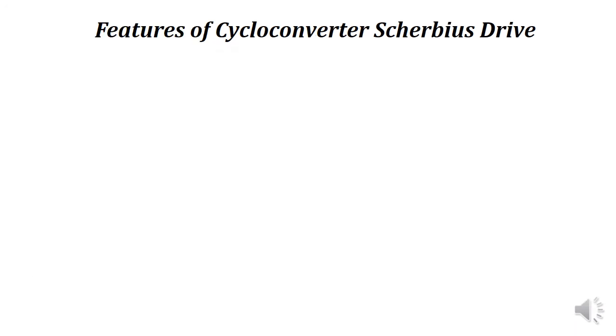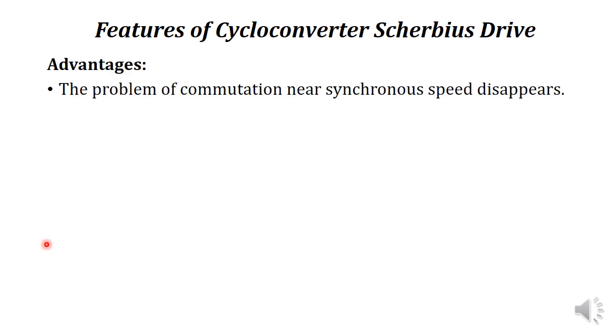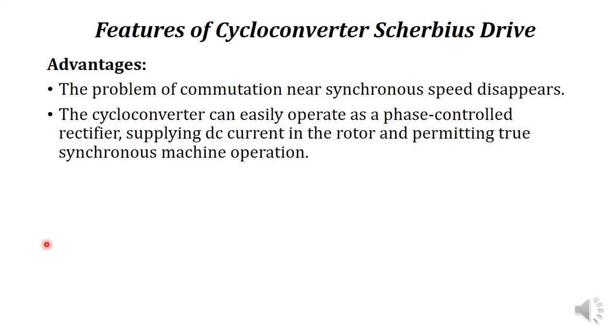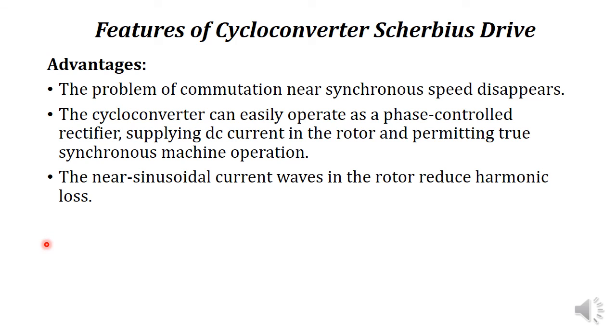Now we will discuss the features of the cycloconverter Scherbius drive — its advantages. First, the commutation problem experienced in the DC-link Scherbius drive near synchronous speed is not present in the cycloconverter Scherbius drive. Second, the cycloconverter can easily operate as a phase-controlled rectifier supplying DC current in the rotor and permitting true synchronous machine operation. Third, the near-sinusoidal current waveforms in the rotor reduce harmonic losses.